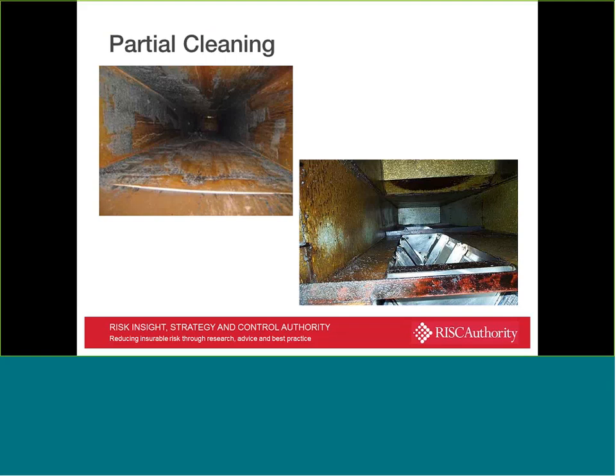A couple of examples there: on the top left-hand side, partial cleaning for no good reason in real terms. On the right-hand side, you can see that one side of the duct has been cleaned, the other side hasn't. Maybe more due to the fact that it's easier to reach certain places than others, or alternatively that the contractor is just not doing a proper job.